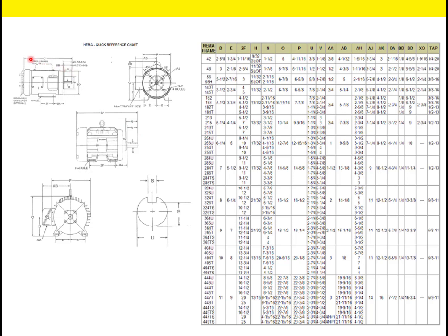Now you have the distance between the feet, right? If you look at this 2F, where my little laser pointer is, hope it's working, 2F is the distance between the bolt holes where the motor is mounted. Same guy, 143T, there it is: 2F, 4 inches. So when you go to order a motor, you know it's going to fit in the same spot where your old motor was. Now you've got to be careful.